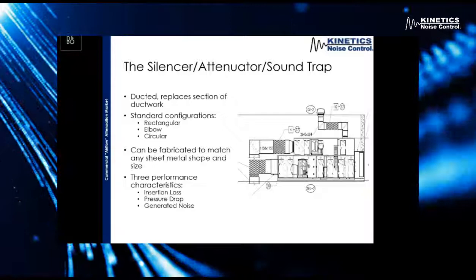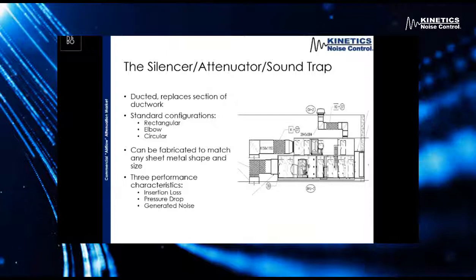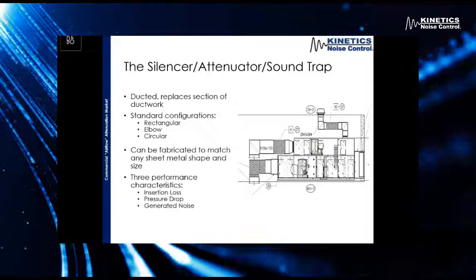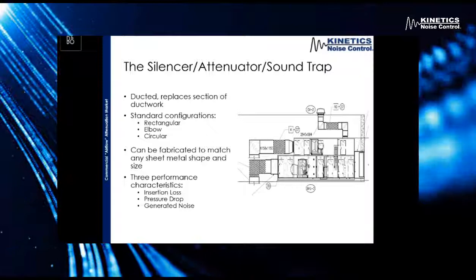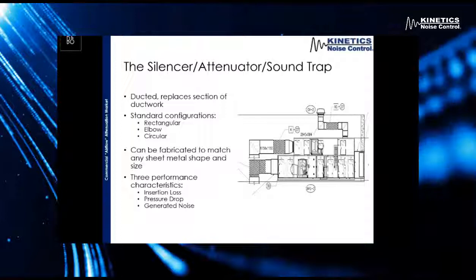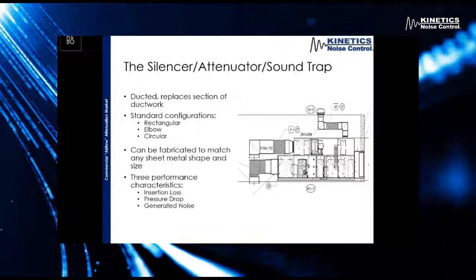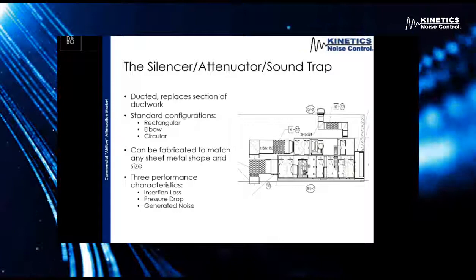So what is a silencer? I call it a silencer — some people call it an attenuator, it could be a sound trap. This tends to be a regional thing, but they all refer to the same piece of equipment. What it is, is it's designed to replace a piece of ductwork. Looking at the image on the right of the slide, those hatched areas are silencers used to apply return and exhaust air for that air handling unit. Our standard configurations for a silencer are rectangular, elbow, and circular, but we can pretty much fabricate these out of anything we can make with sheet metal — we have a lot of variation in custom designs we can do.